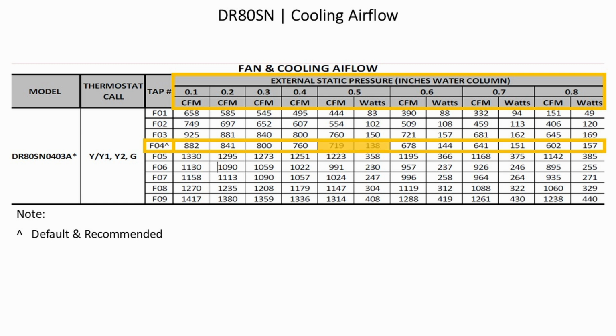For example, at the F04 fan speed, at 0.5 inches of water column static pressure, there is 719 CFM using 138 watts of power. At 0.7 inches of water column static pressure, the CFM drops down to 641 and the watts used goes up to 151.